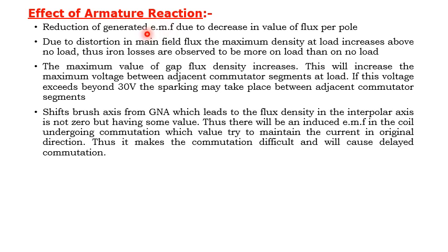As you know already, due to the demagnetization effect of armature reaction, there will be a reduction of the magnitude of the flux per pole. Due to the reduction of the magnitude of the flux per pole, there will be a reduction of generated EMF. So this is one effect of armature reaction.